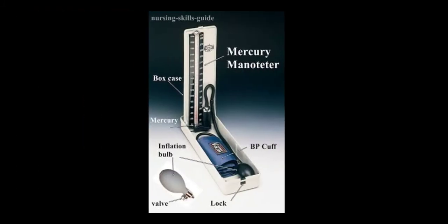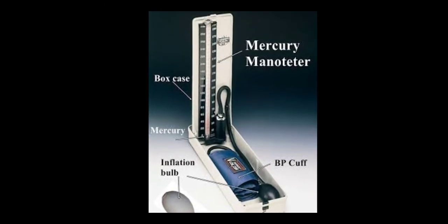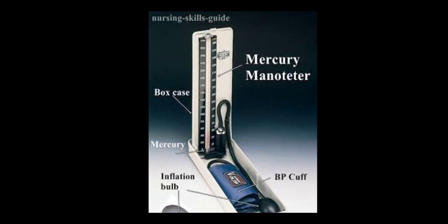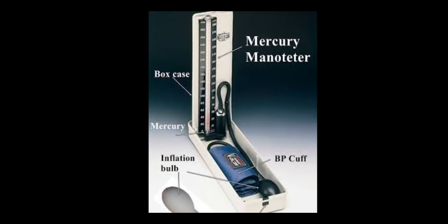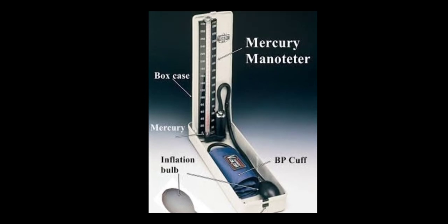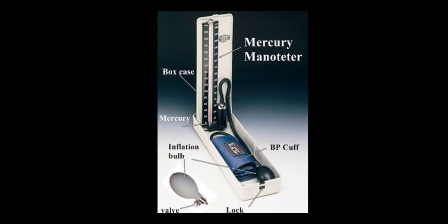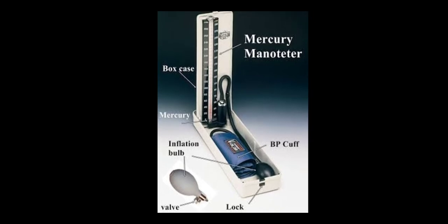Next is the mercury sphygmomanometer. In the mercury sphygmomanometer, mercury forms the column for measuring blood pressure. The mercury column will rise when we inflate the bulb. These are the parts of the mercury sphygmomanometer.